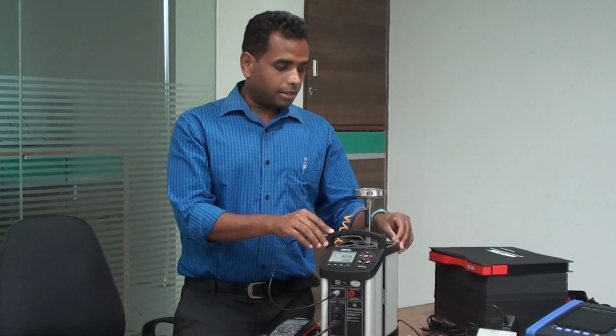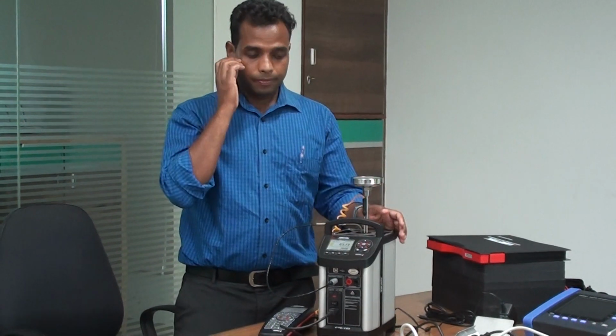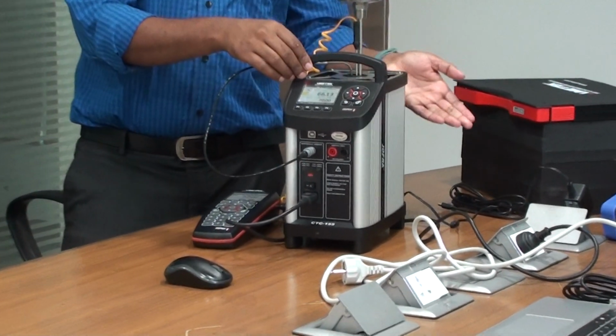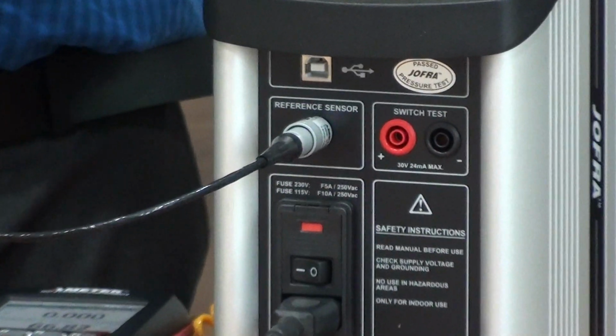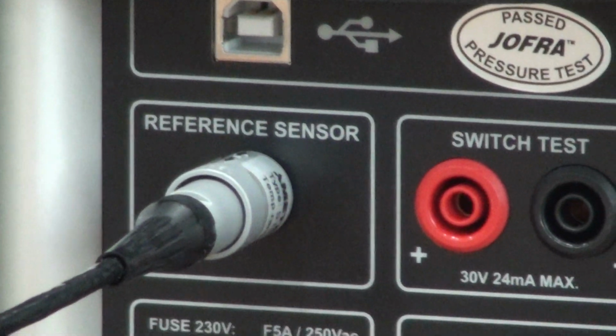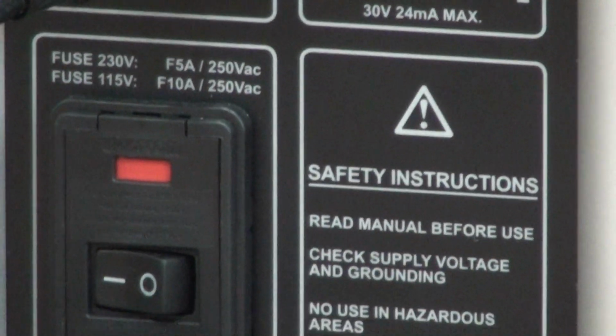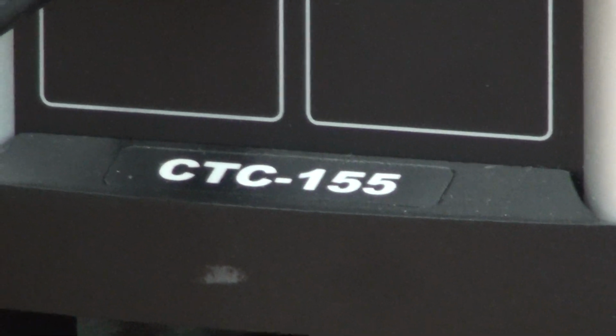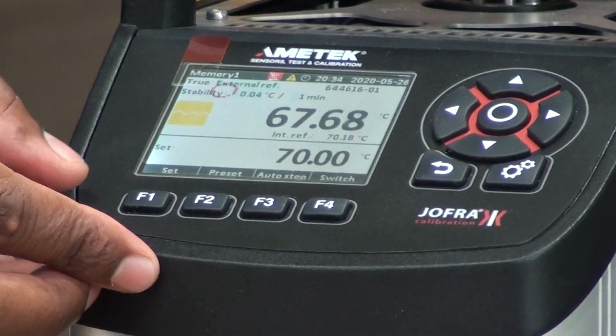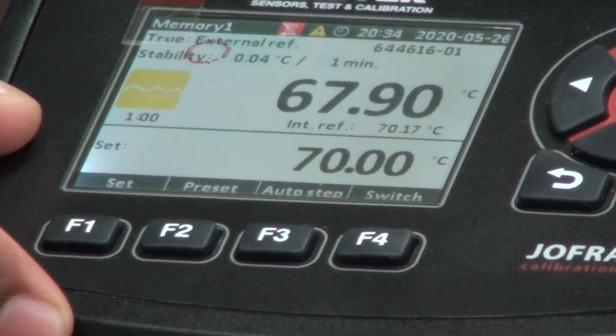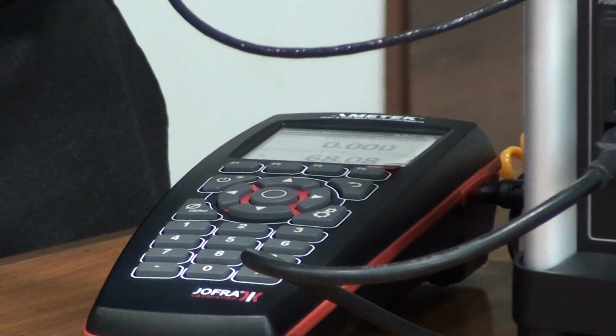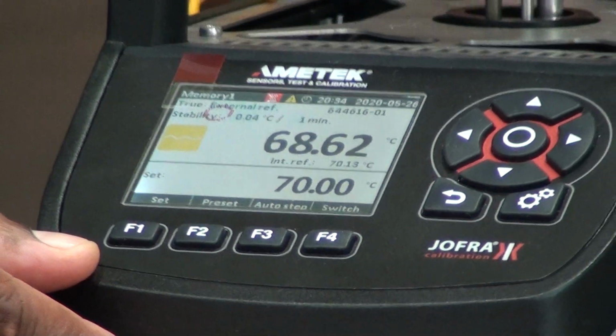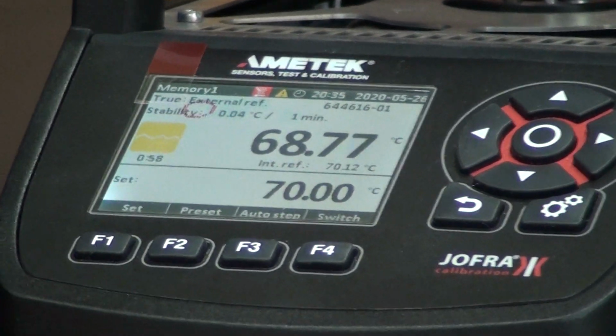that has to be replaced. Or if you want to check the open and closed circuit, set the temperature, the pass fail, the lower limit, upper limit. If the temperature increases beyond 60, the switch will be closed. If it is within the set limit, the switch will be open. This feature is there in this instrument. Now it is about to stabilize. It will take some more time.